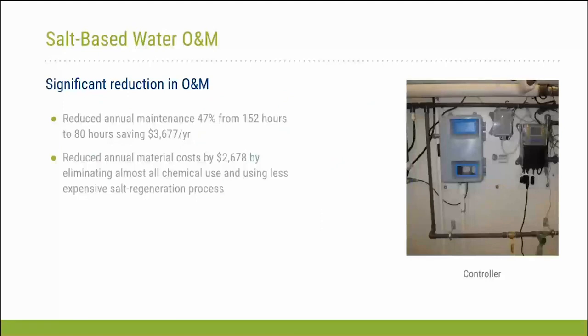Yeah, so this one also had a reduction in O&M. There was a 47% reduction in the total O&M hours for the product. The savings was $3,677 per year. And then similar to the DWT demonstration, there was also the elimination of the chemical costs. I think actually this system maybe still did use a small amount of biocide, and Tyler and Doug can correct me if I was wrong on that one, but there was a very significant reduction in the chemical treatment, and you see that in the cost that's listed there. Okay, next slide.